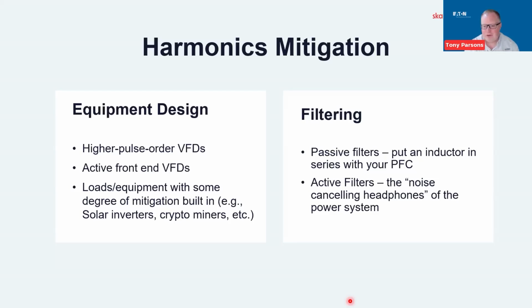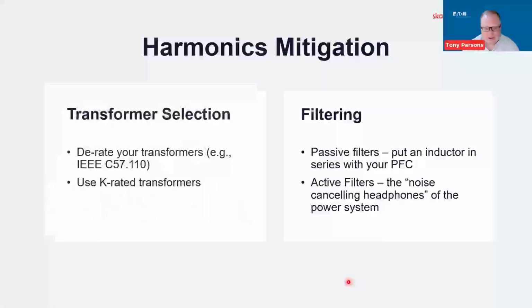Think about what your noise canceling headphones do, right? They've got a microphone. They're kind of listening for the ambient noise and, you may not think of it this way, but they're actually injecting the opposite of that noise, right? To help cancel it out, whether you're on the airplane or the train or whatever, to try to make it a little less noisy, at least in your head. The active filter can do the same thing. Look at and measure the harmonic content of your distorting loads and inject current that is out of phase with it so that it cancels and looks much cleaner to the rest of the system.